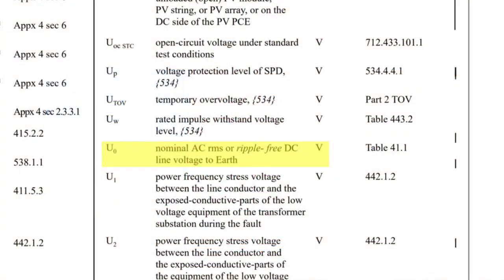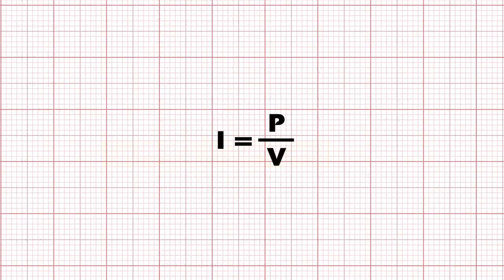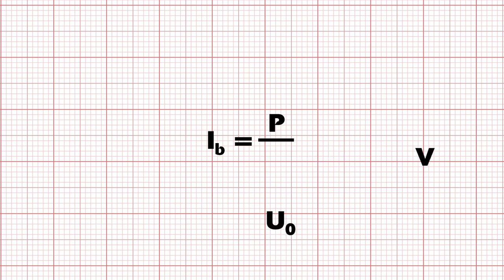U0 represents the nominal AC RMS line voltage to earth — in other words, the nominal voltage. So we'll change the I to IB (I with a lowercase b in the subscript), which now means the design current of the circuit. And we'll change the V to U0 (U with a zero in the subscript) to mean nominal voltage. In the UK it will have a value of 230 volts AC. So our formula is now: IB equals P over U0, or design current equals power over nominal voltage.